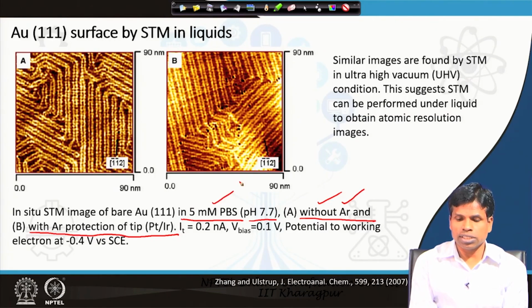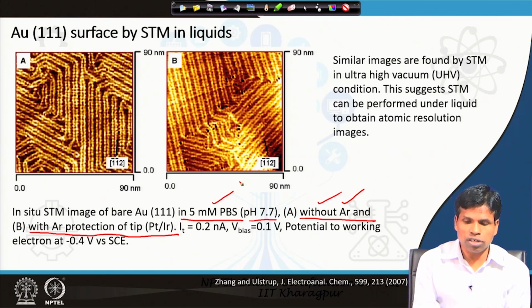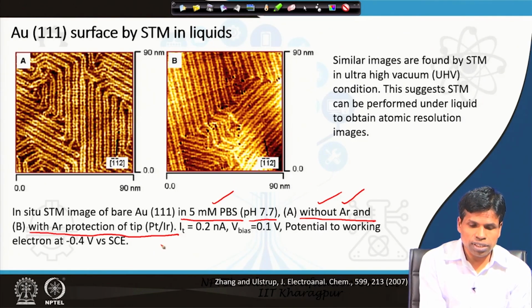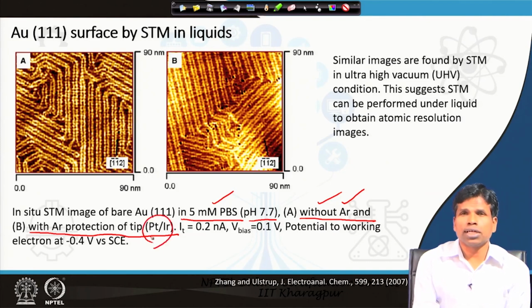So, the oxygen presence in the solution or in the medium has not much impact as far as the quality of the image is concerned. This image was collected using a platinum iridium tip, because a platinum iridium tip can be utilized as it is more inert in the solution compared to the tungsten tip, which can form oxide, and once it forms oxide, the tunneling current measurements are not possible because of the low conductivity of oxide.